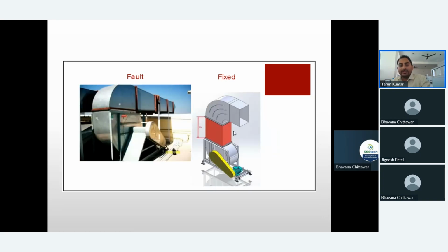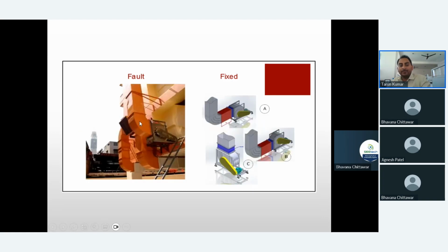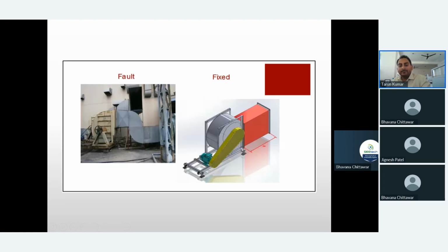At the same time, you can see this example also. We would have gone with some length of straight duct, and after that some bend, rather than going with an immediate bend over the fan. Here you can see the installation. Typically, there are three kinds of better installation shown in the photograph. Either they would have gone with the top discharge directly, rather than going with the 90-degree, to avoid the pressure loss within the fan.